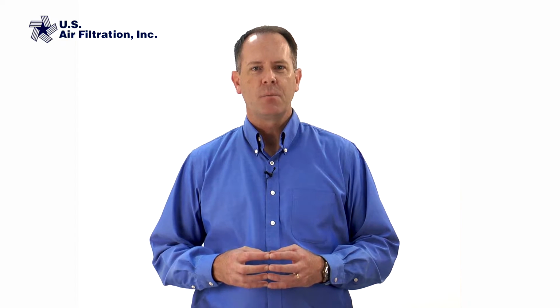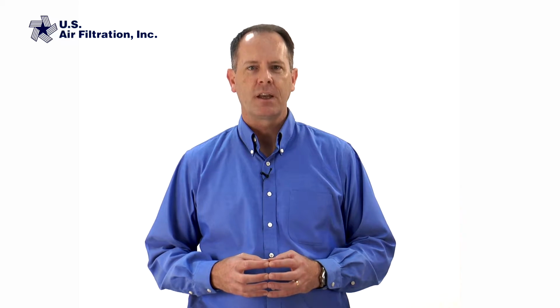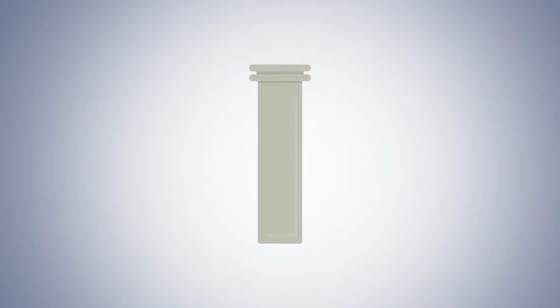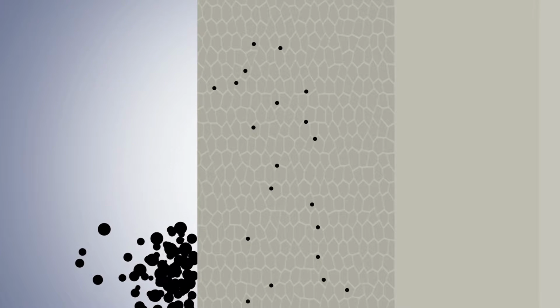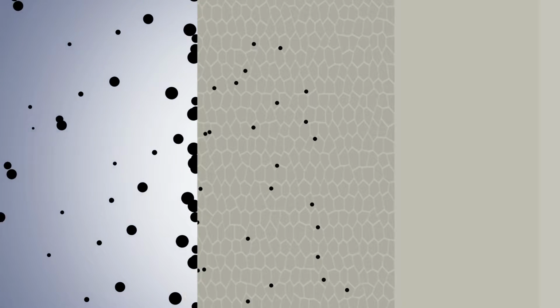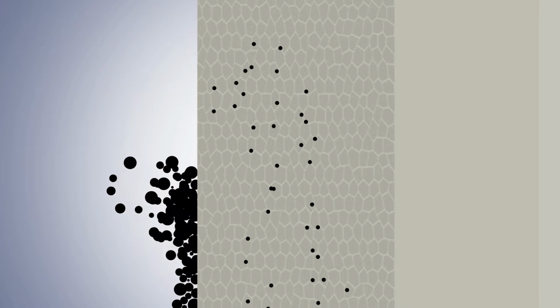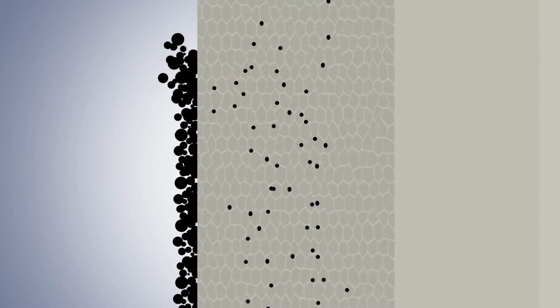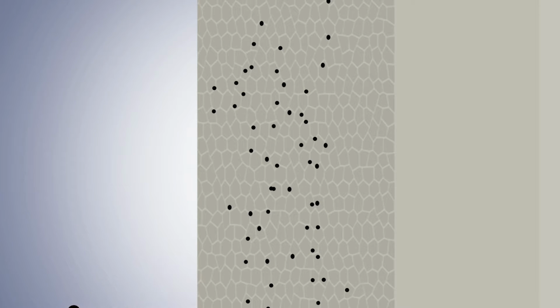To understand how PTFE membrane bags can accomplish these things, let's first look at how a standard filter bag works. On a standard bag, dust builds up on the outside of the bag and creates what is known as the filter cake. The filter cake actually does the filtering, while the bag fabric acts only as a support for the cake. When the bags are pulsed, most of the filter cake releases and the buildup of dust begins again. Over time, however, some of the dust gets embedded deep into the bag fibers. Eventually, the bags will completely plug and need to be replaced.